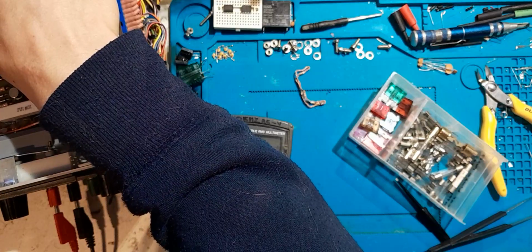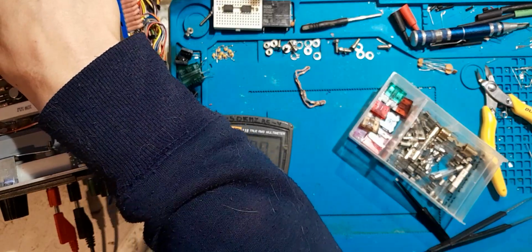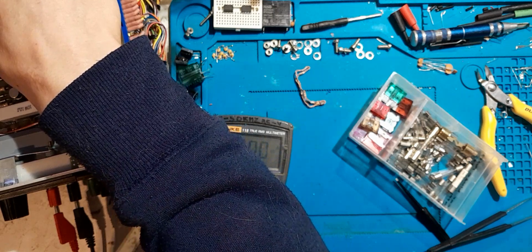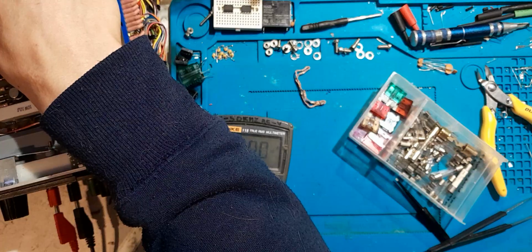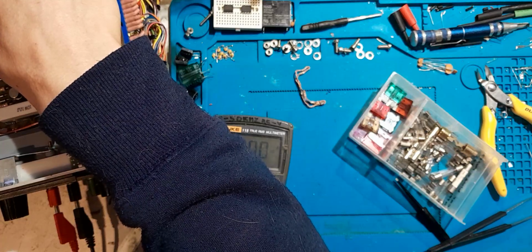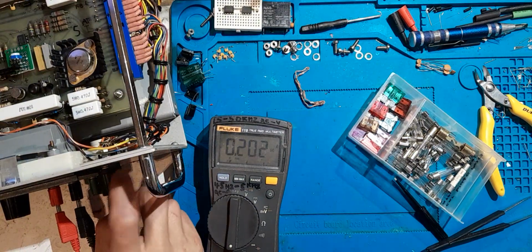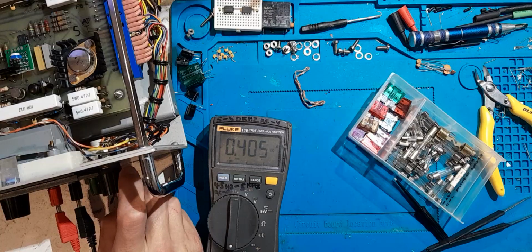I'm doing this at a low current, by the way, because if I do it at 1 amp, the current resistor will warm up and the current will be slowly drifting, which will be very hard to calibrate whilst it's drifting, right? So I figured I'd do it like this and then check it. Alright, now I'm going to wind it up. 400, and we've got 400 on the meter, that's good.